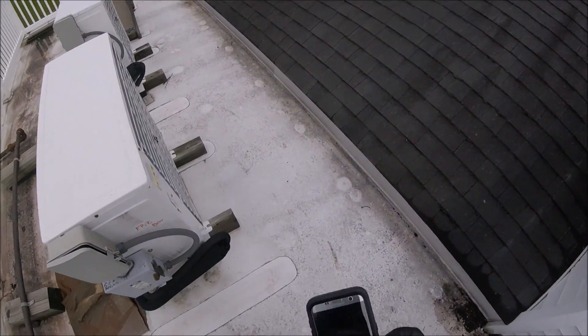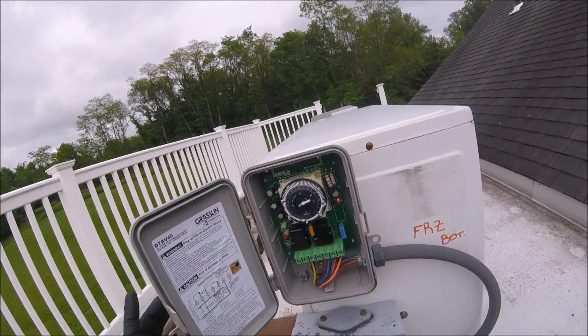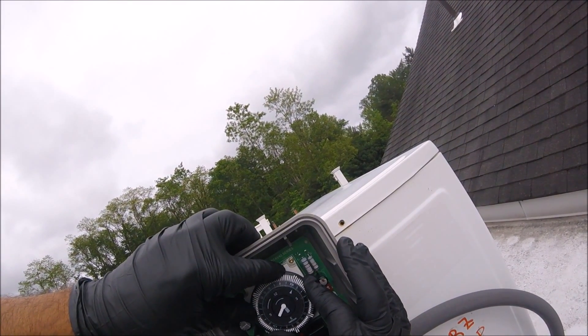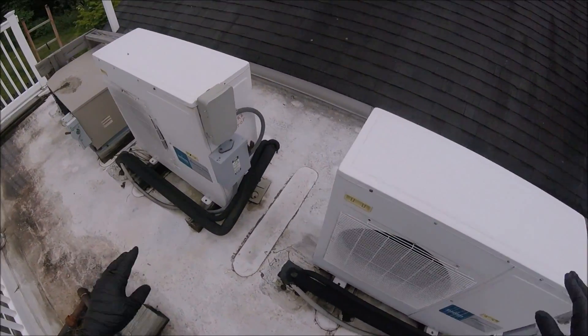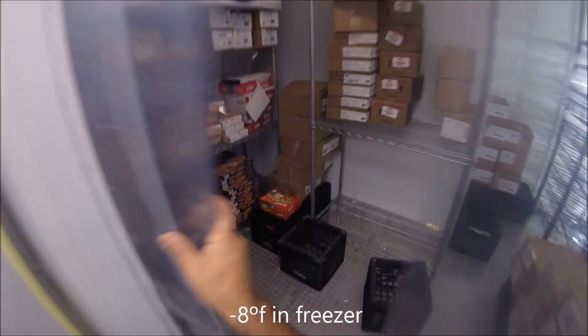There you go. I just passed the defrost cycle to the first pin on both units. Now they're both going to be running — freezing and defrosting together. The temperature right now is about minus eight, minus seven degrees. Both of them running. Good to go. Let's go back home. Thank you for watching, guys.